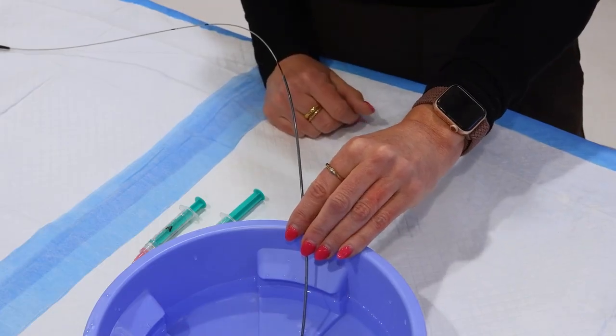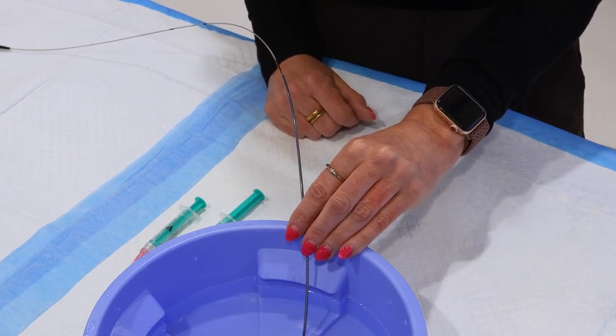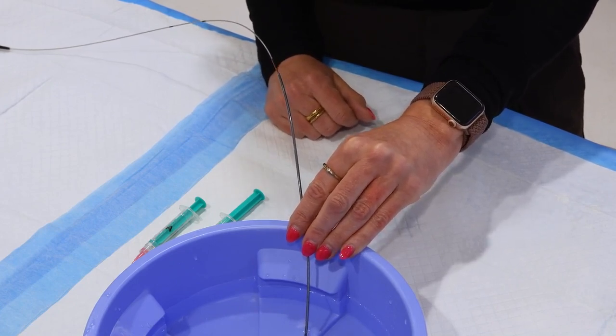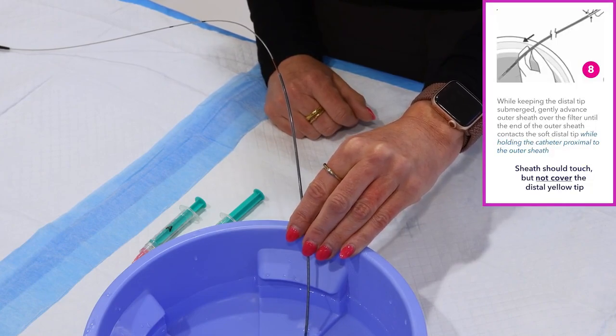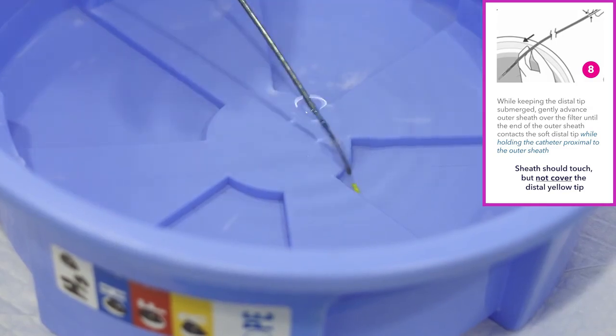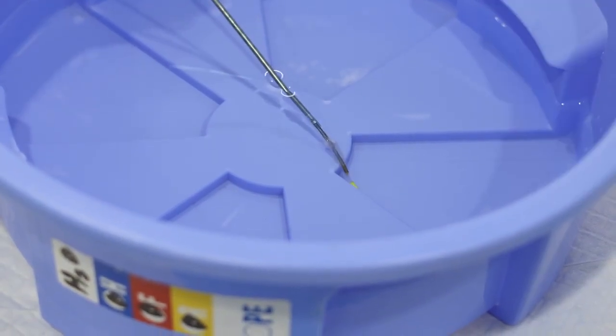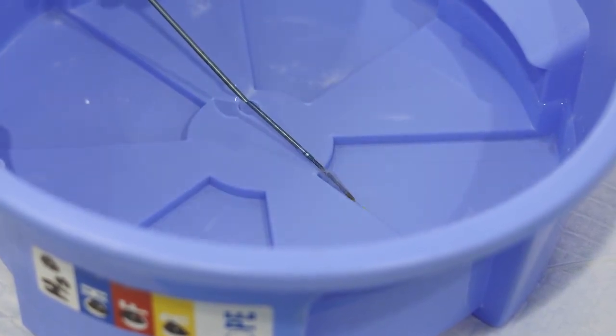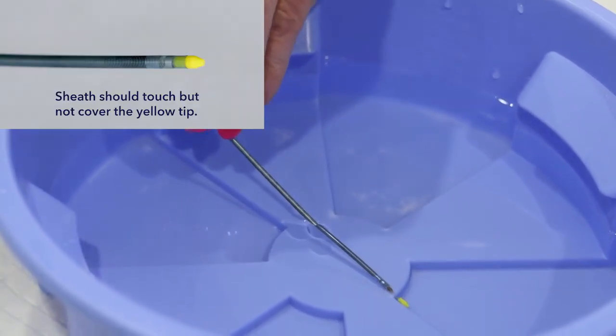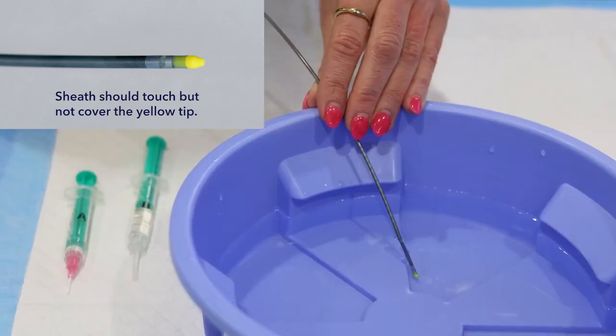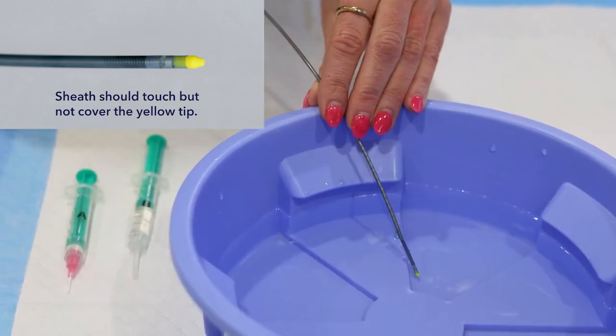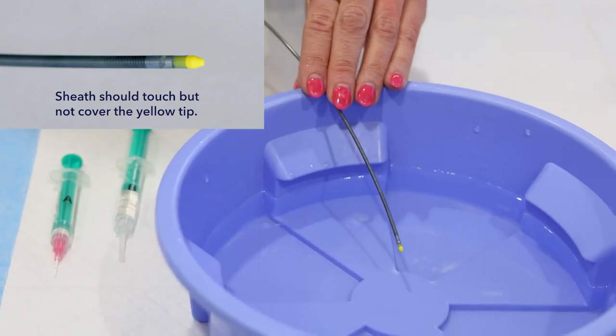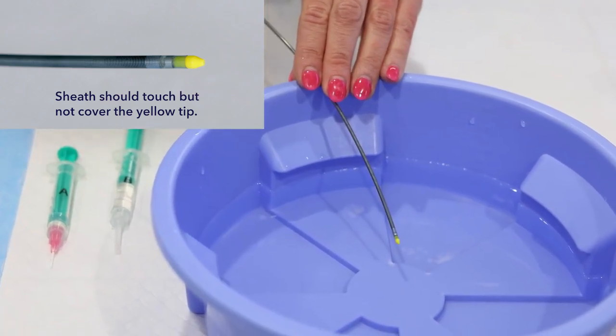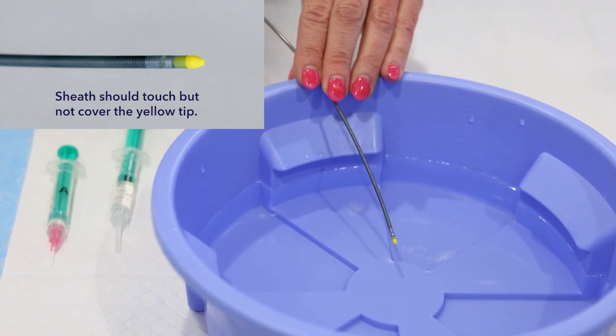While keeping the distal end submerged in saline, hold the catheter tubing of the blue outer sheath and using a slow, steady pressure, gently advance the outer blue sheath over the filter until the end of the outer blue sheath contacts the soft distal tip while holding the catheter proximal to the outer sheath. Make sure not to cover the yellow nose cone. Always make sure that the sheath is moving towards the yellow tip. Moving the outer sheath in the opposite direction can result in inadvertent release of the stent.